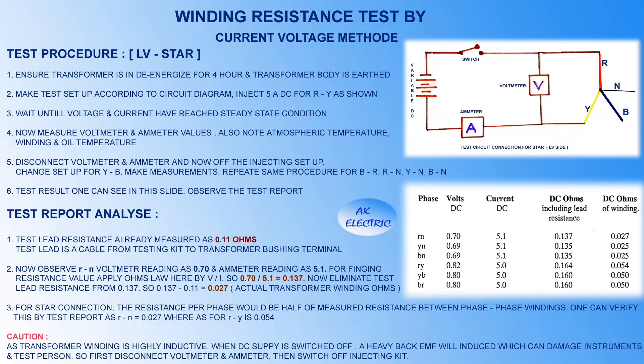Now we will start analyzing the test report. Test lead resistance is already measured as 0.11 ohm. The test lead is a cable from the testing kit to the transformer bushing terminal. Observe R-to-N: voltmeter reading is 0.70 and ammeter reading is 5.1. For finding resistance value, apply Ohm's law: V divided by I. So 0.70 divided by 5.1 gives us 0.137. Now eliminate the test lead resistance: 0.137 minus 0.11 gives us 0.027 ohm, which is the actual transformer winding resistance.